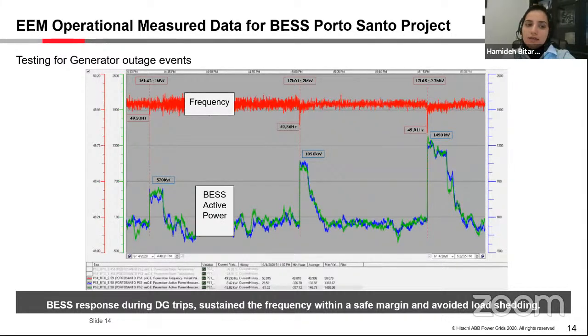Okay, so the next slide is again related to our BESS project for Porto Santo, and as you can see, it is related to a contingency of generator outage event. What happened here is the time window is 40 minutes, and you see the measured operational data for the frequency, and we had 3 generator outages during these events.